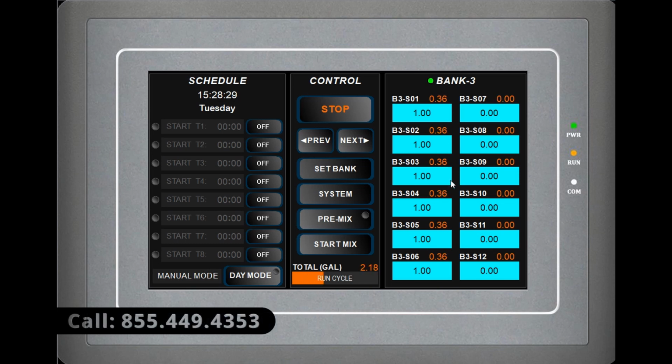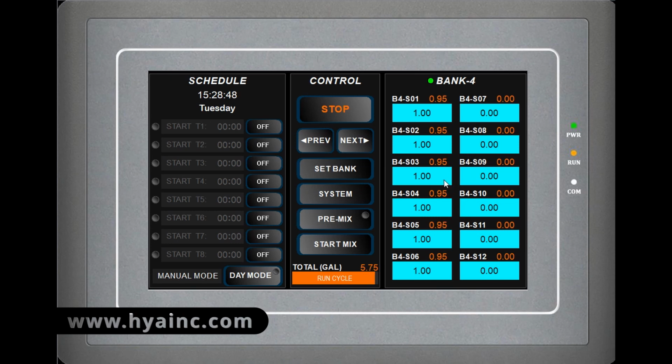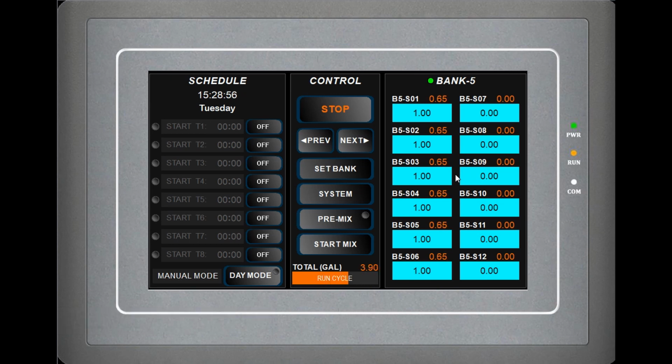And the reason is all we really need to know is how long it takes to water 6 valves, because it's almost always a water supply problem. Like how long does it take that supply to get to that bank? And we find that the first set of 6 is fine. That's why it's super important, if you only have 8 valves, to run the first set of 6, because otherwise it'll calibrate itself to only 5 or 4 or whatever. So it's running the first set of 6. It's teaching each bank how long is appropriate for a set of 6 valves to be open at any given time.